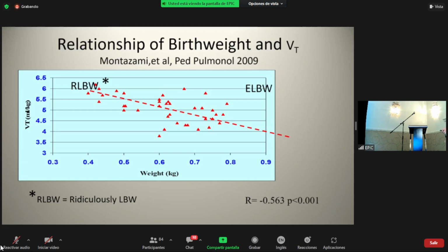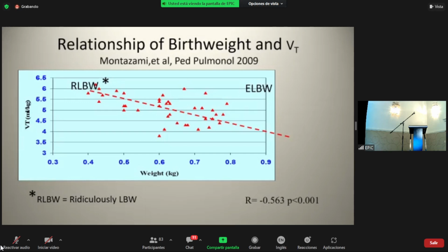When you go down to the lower end, what I call the ridiculously low birth weight infants, they needed a bigger tidal volume. And this has to do with the dead space of the flow sensor. So if you're using the servo with a PRVC without measuring the tidal volume, without having the flow sensor proximally, this would not apply. But with VG, where we think it's important to measure tidal volume at the airway opening, the dead space of the flow sensor becomes more significant the smaller the baby. So the dead space of 0.8 ml is a certain percentage of the tidal volume at 800 grams. It's a twice as large proportion of the tidal volume at 400 grams. But because there's some admixture of fresh gas and dead space gas, the tidal volume needed is only a little bit bigger, but it is bigger.